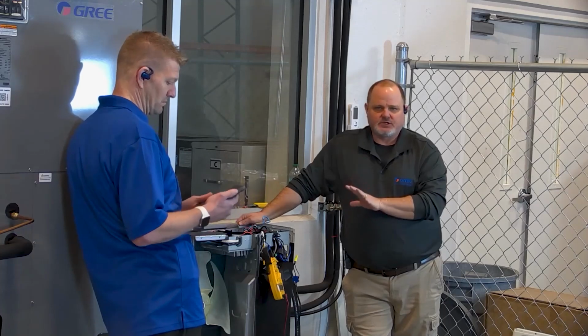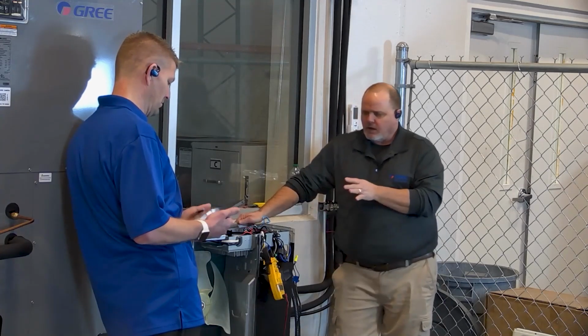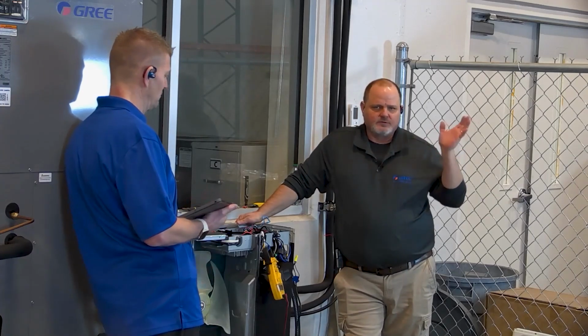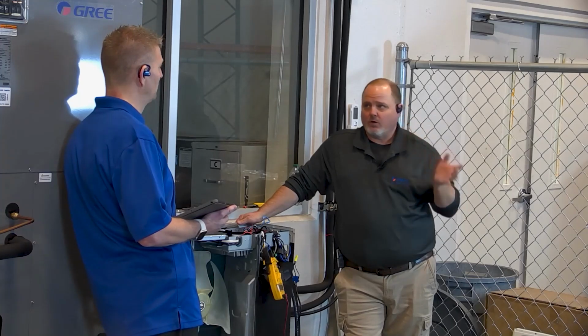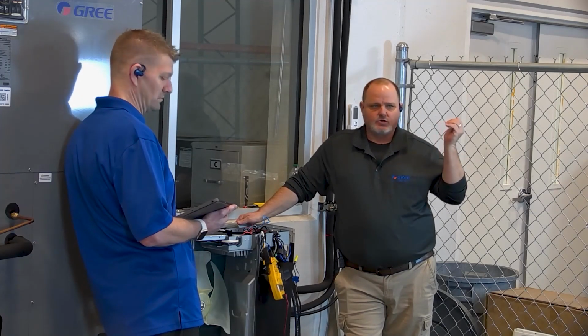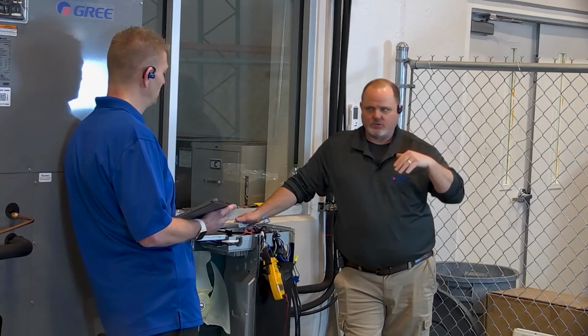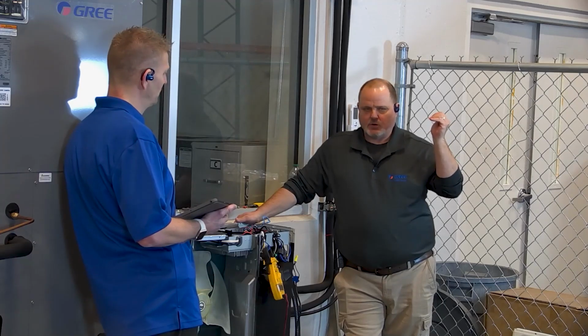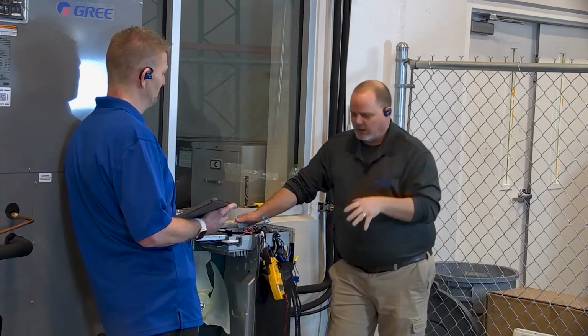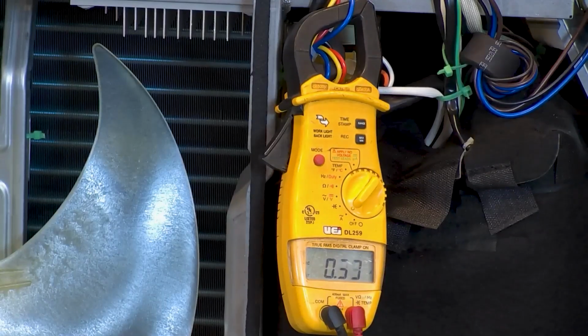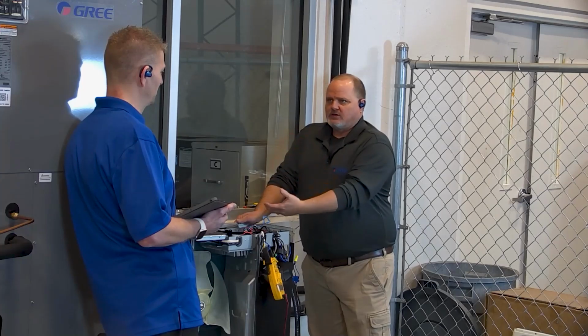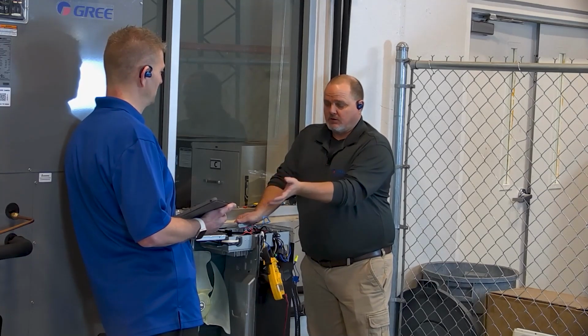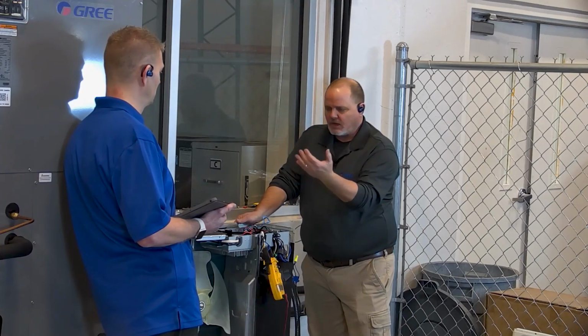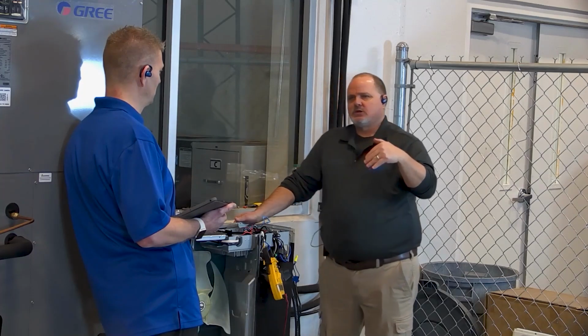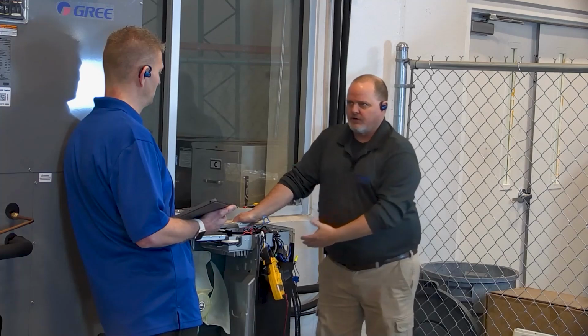These compressors in these machines, this is a 230 volt unit. It uses, and I've talked about it before, there's a video out there about how an inverter driver works that we've done before. It shows you how the IGBTs, the insulated gate bipolar transistors, switches basically create its own three-phase sine wave to run this three-phase compressor. That is a three-phase AC compressor. We are taking single-phase voltage, creating a DC bus. The DC bus is boosted up with the capacitors to give us the high DC bus.